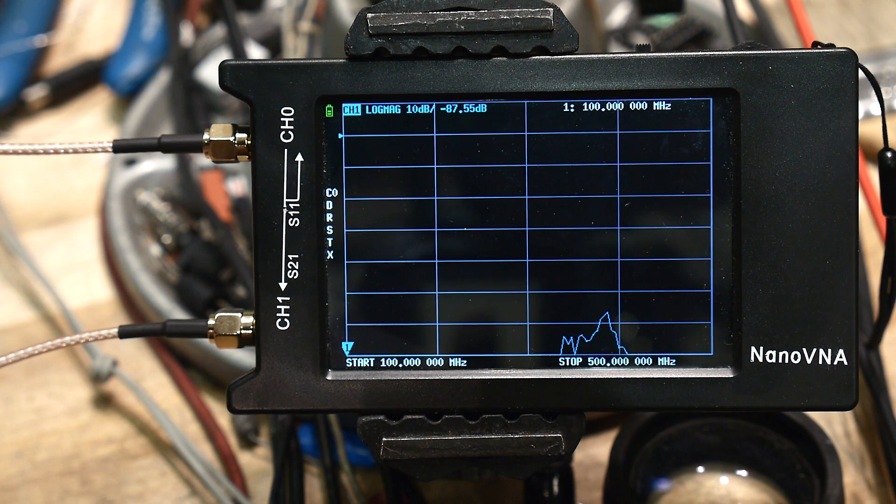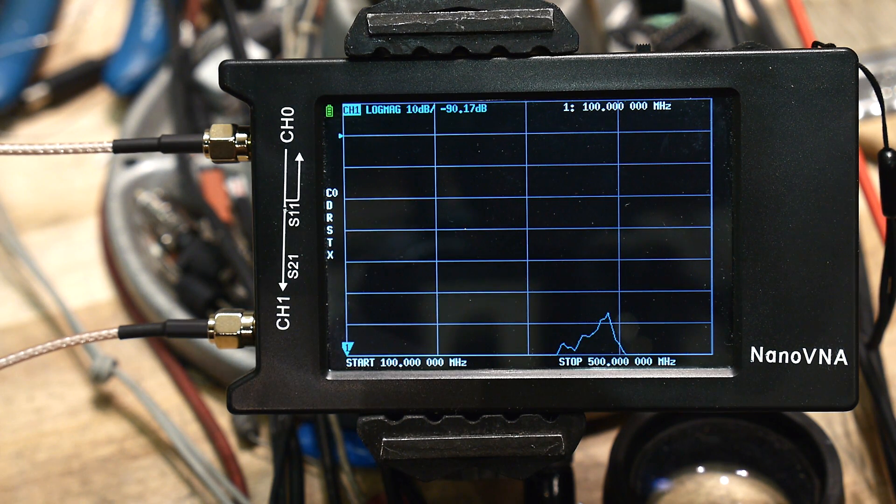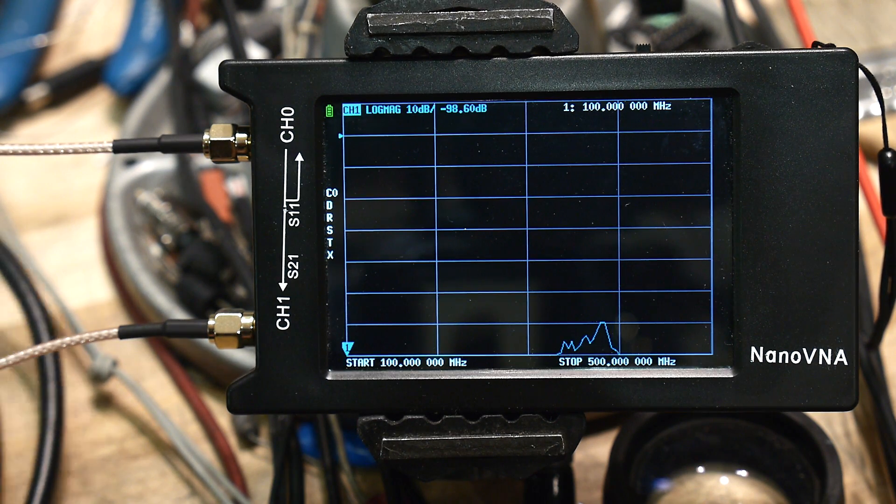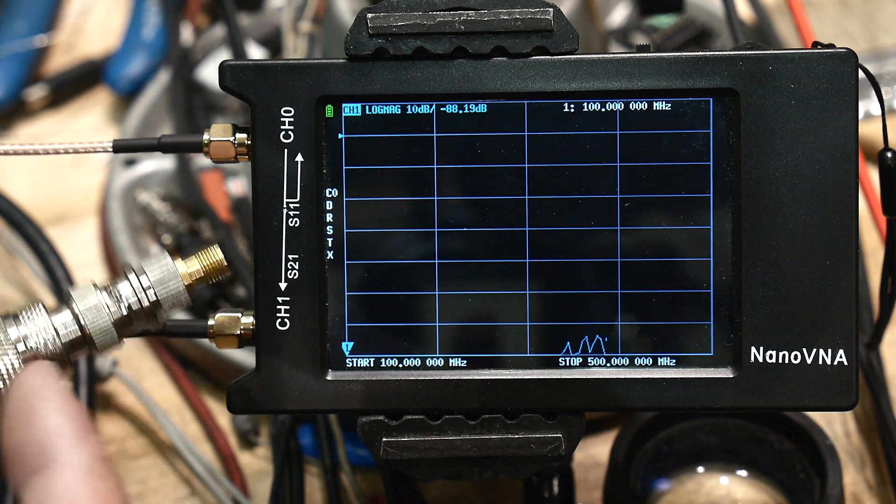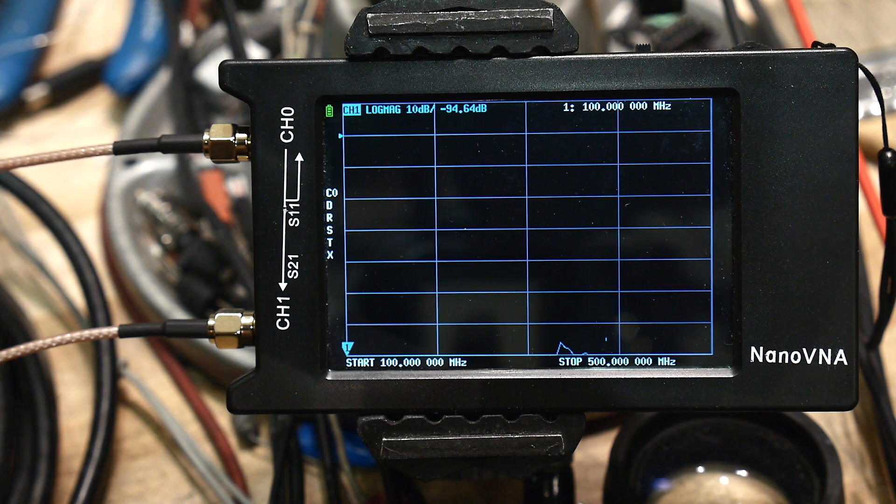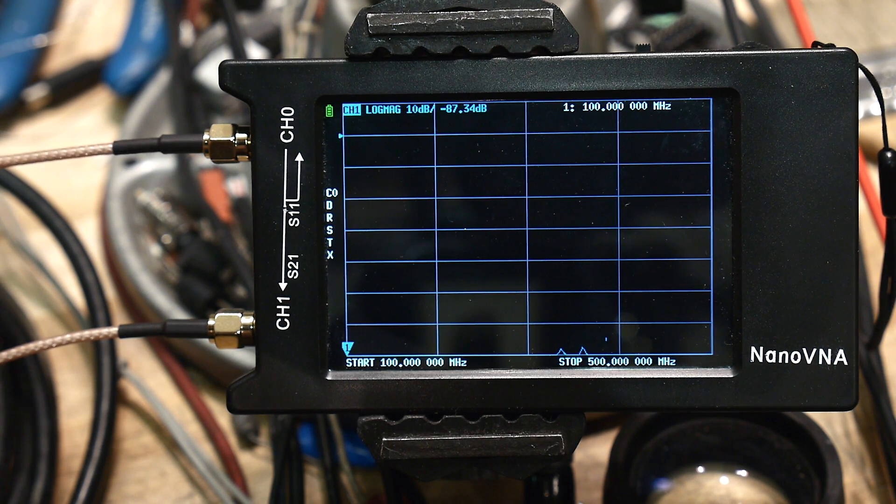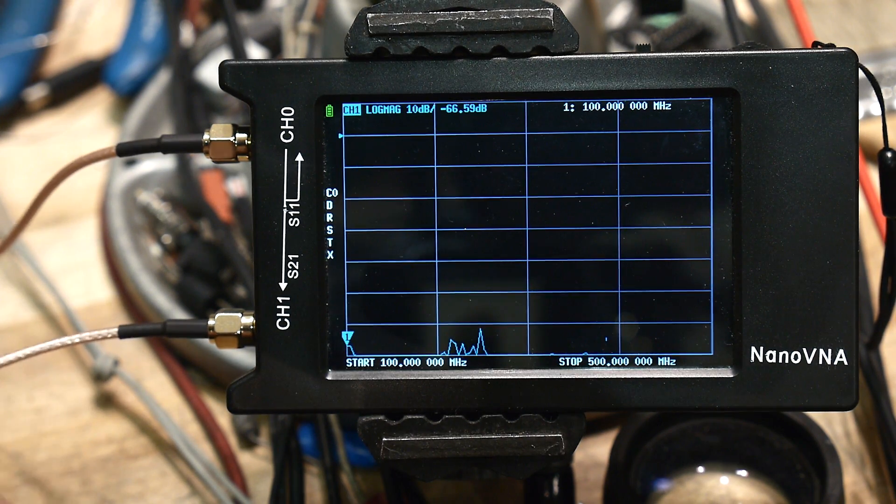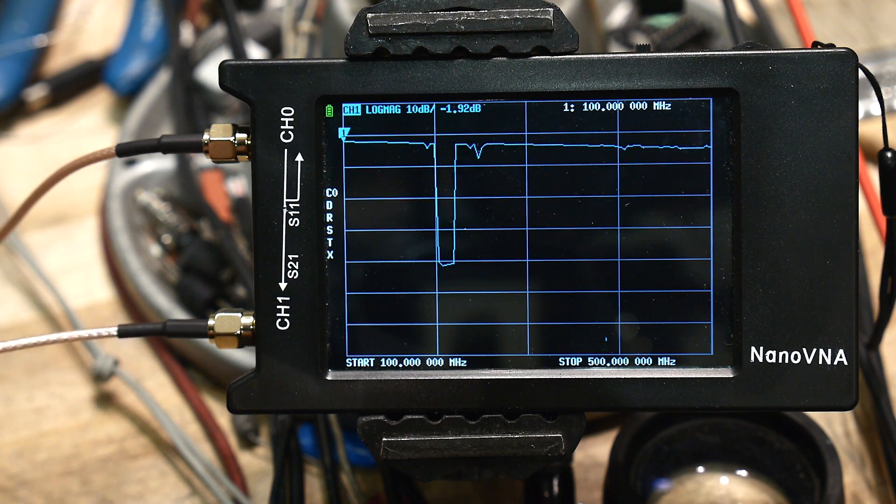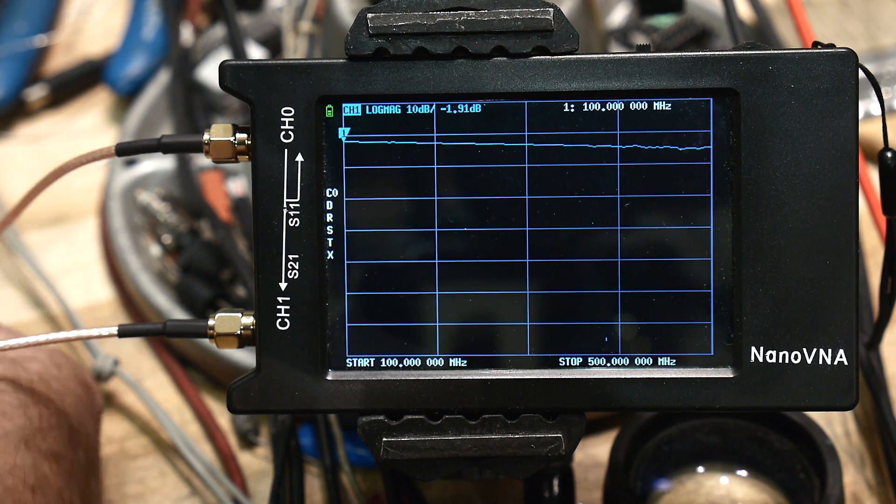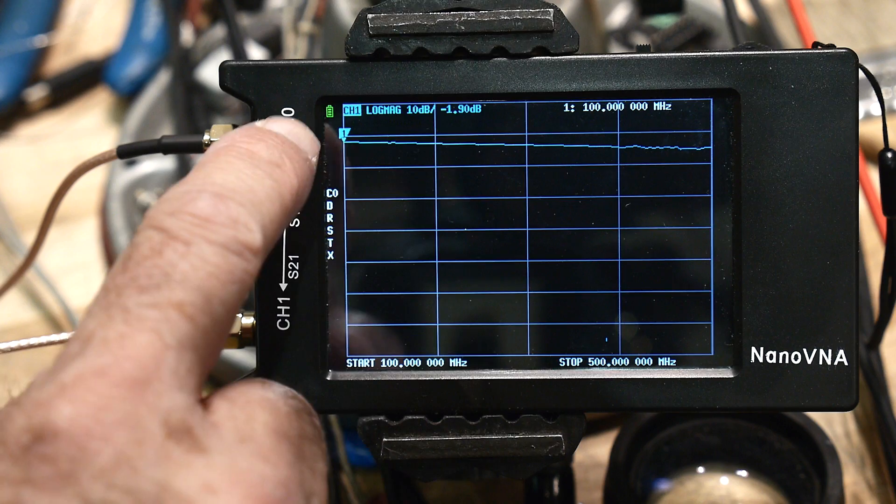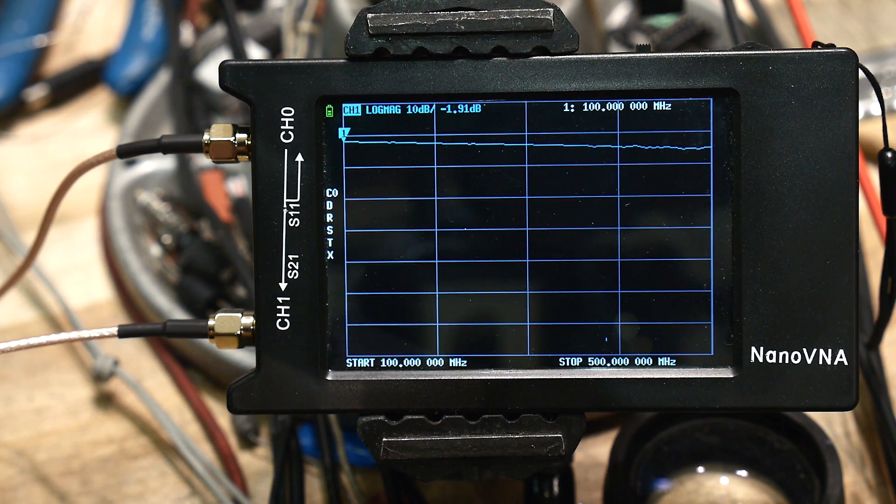Okay, all right, so we are ready to measure. We are all set to go. Let me move these calibration standards out of the way so don't lose them. Let me get my coax. Remember I've got the connectors on them. So I'm going to connect one end to channel 0 and I'm going to connect the other end to channel 1. And we should start to see a trace. There we go. Very good. So now you see that we have a trace but it's not up to where the reference was, it's down a little bit. We're losing a little bit of signal.